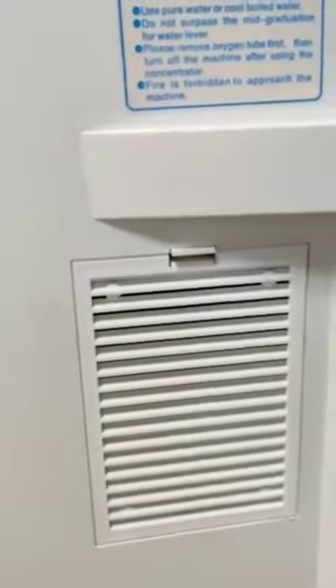On the right side of the oxygen concentrator we have filters which can be replaced from time to time, and one set of extra filters is supplied with the machine. And this is the air filter which has to be installed onto the side of the oxygen concentrator. So this is the method of installing. So now it has been locked. So this is the air filter which we are using, that is taking the atmospheric air.